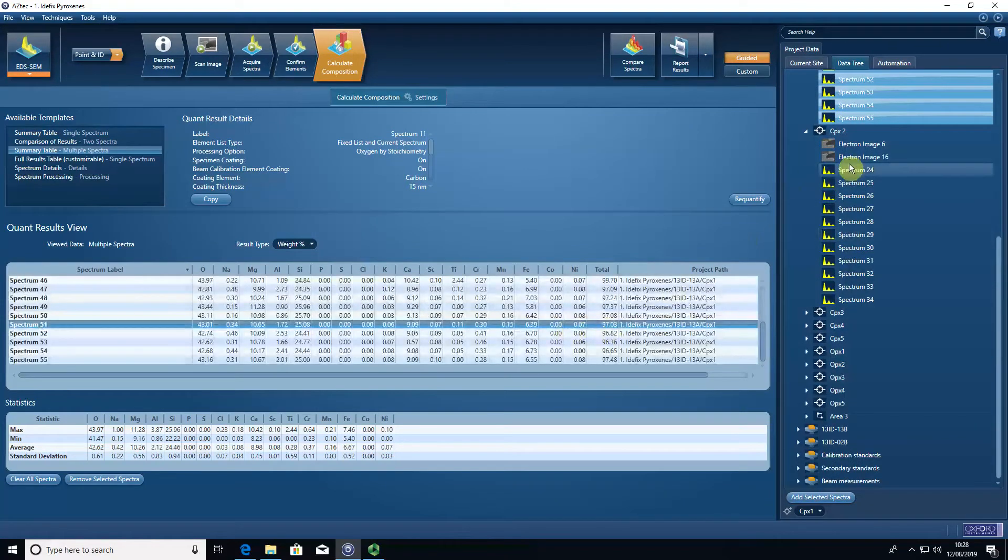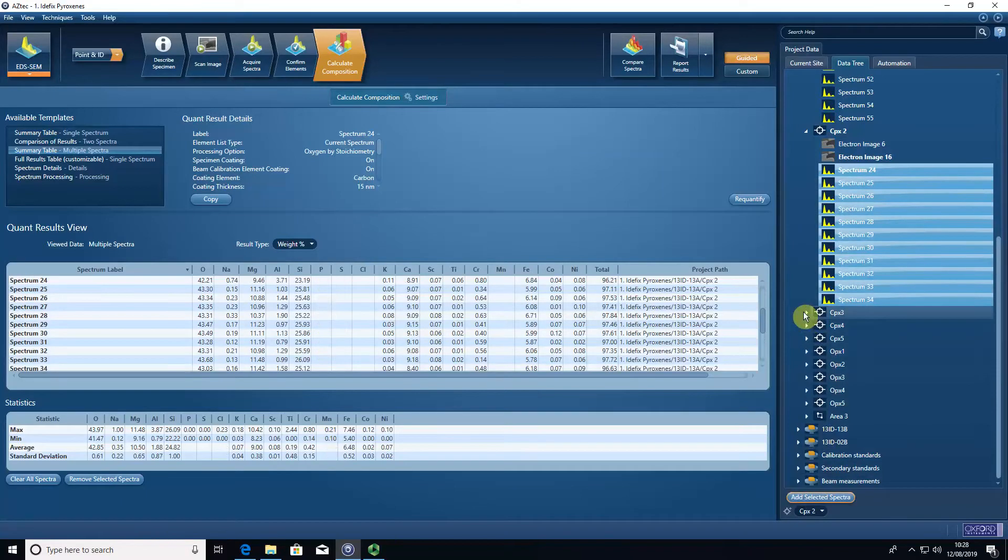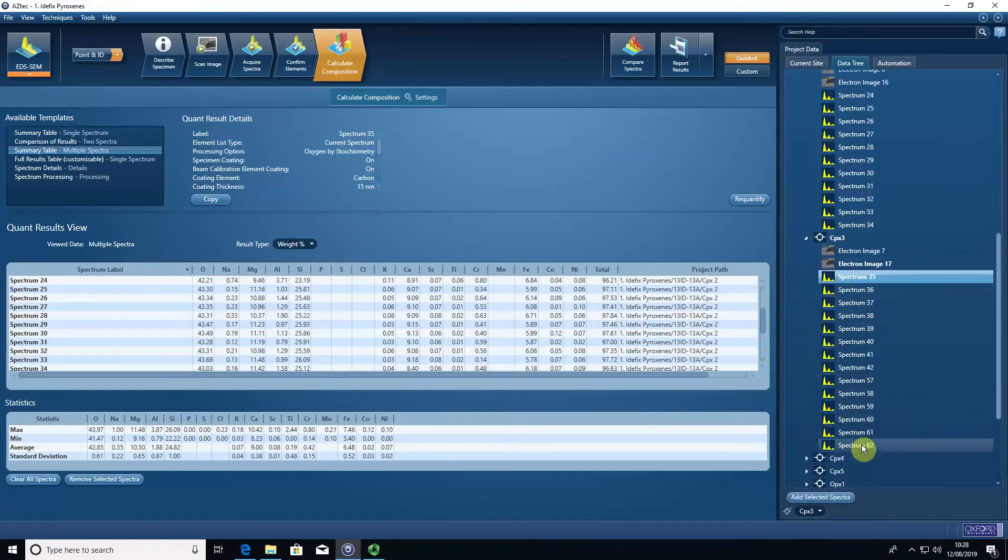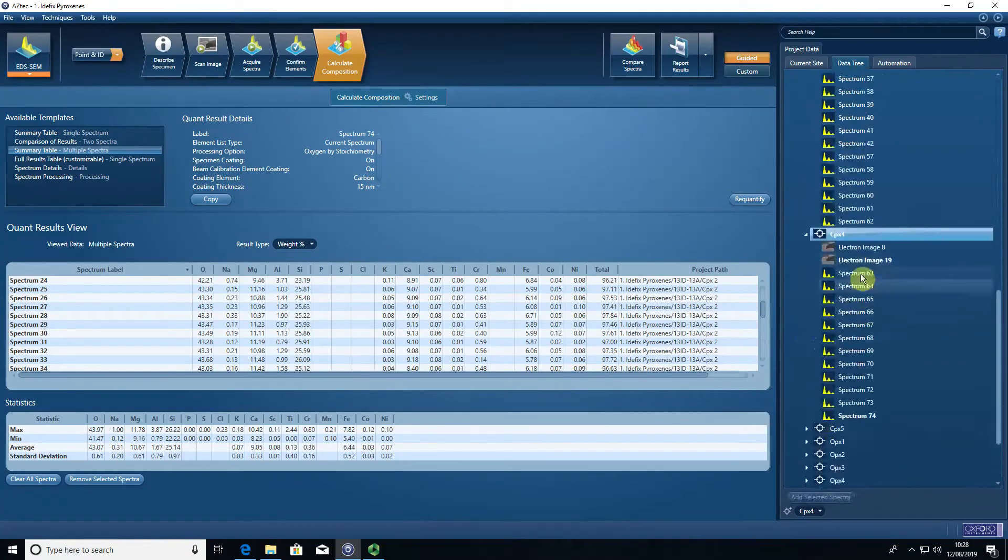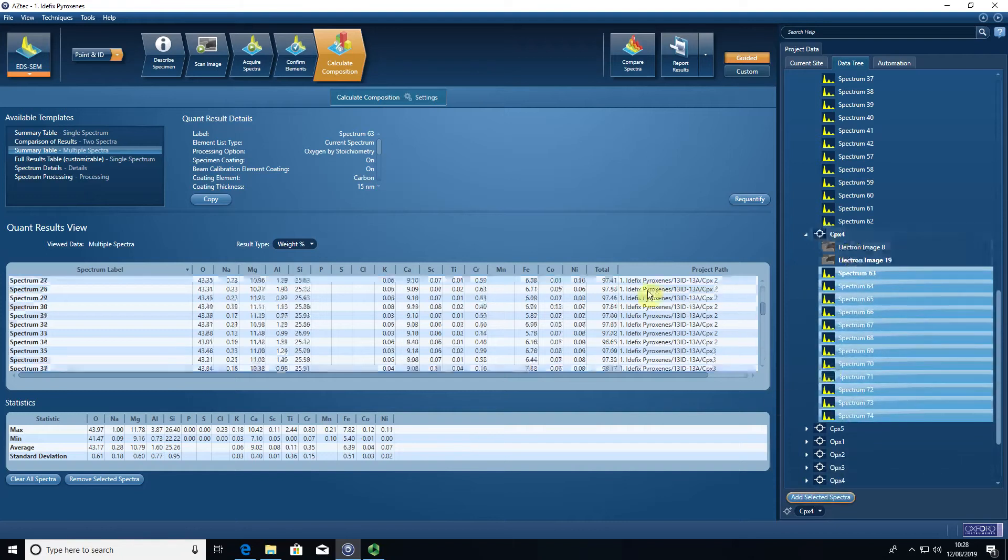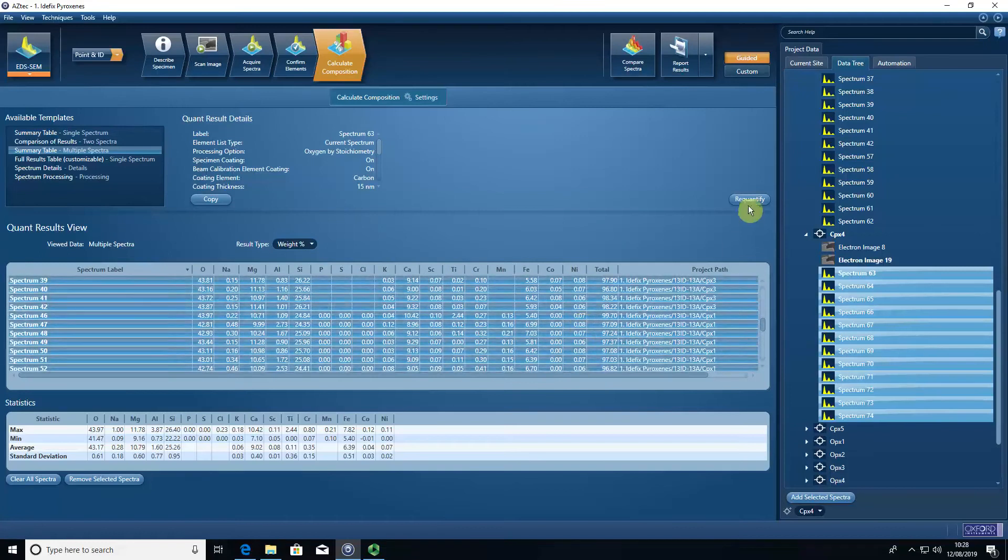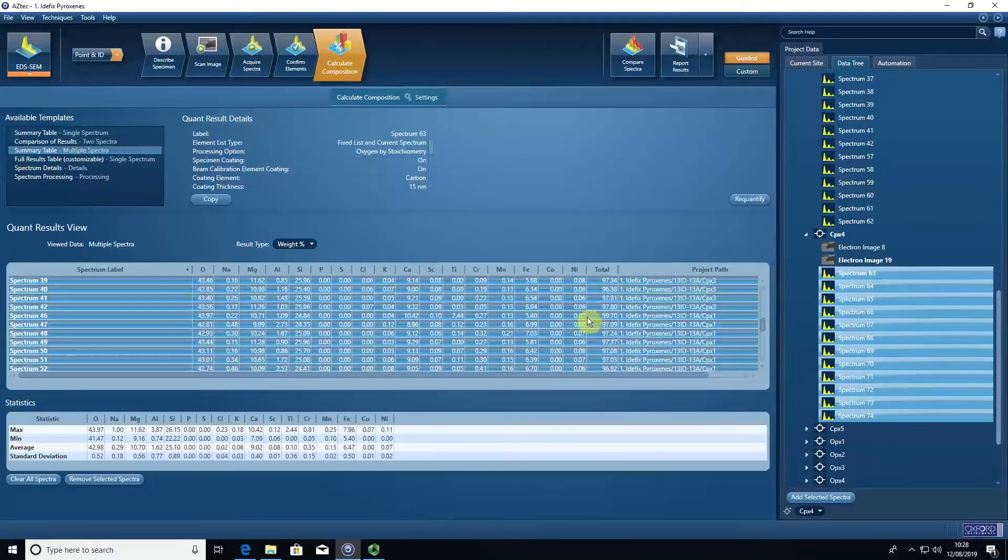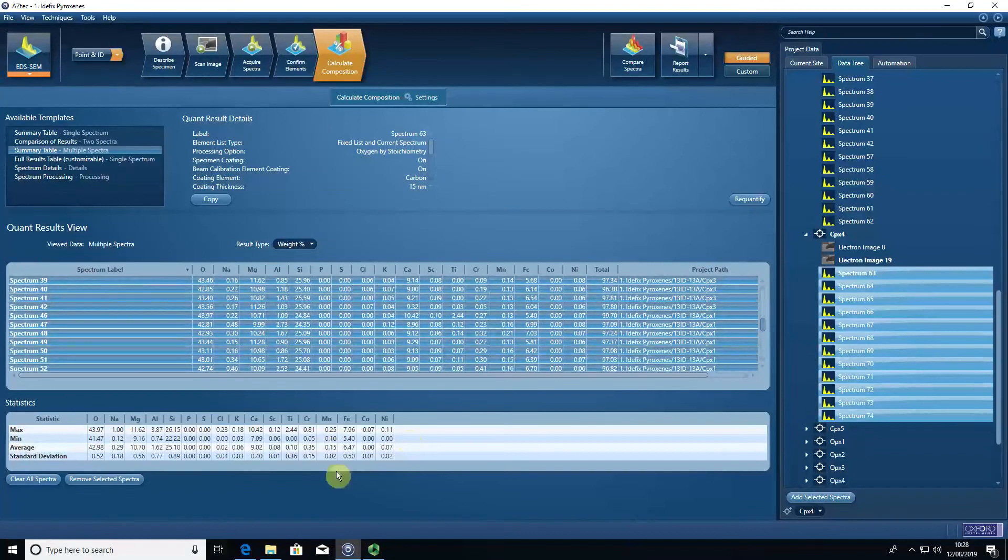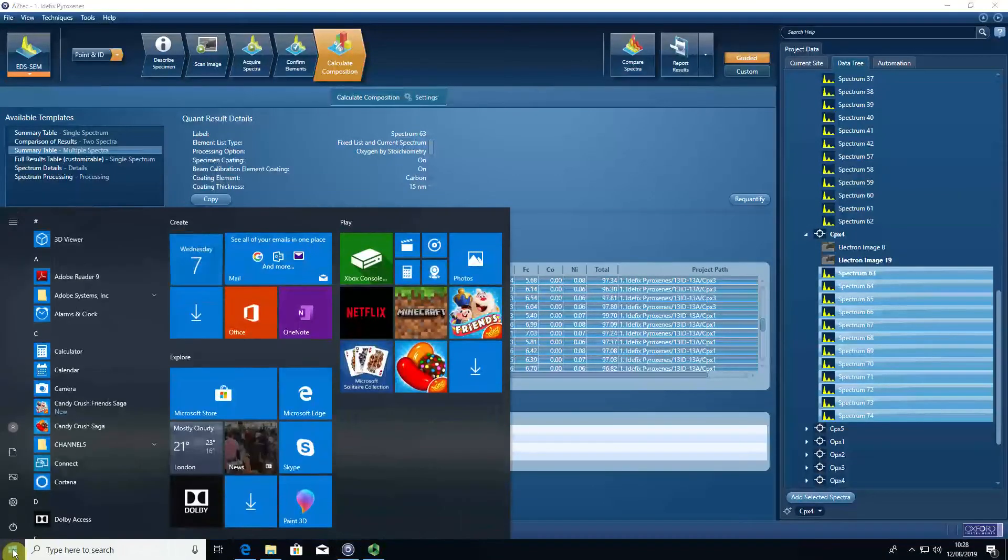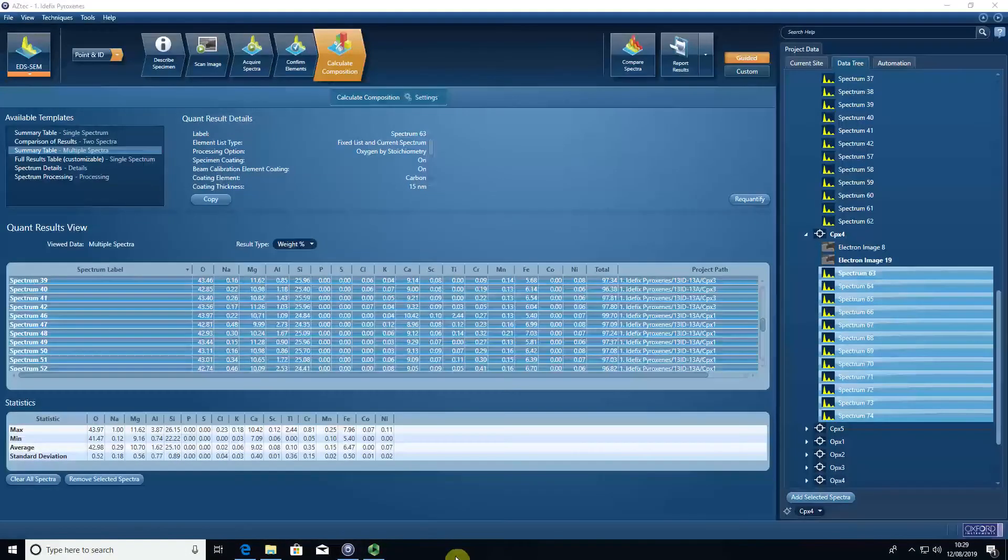The easiest way to do this is to add all your spectra at the very beginning. As I say, it's recommended to do this at the point of acquisition rather than the next day because you never know if someone's going to mess around with your standardization without you knowing by accident. Let's say we've added all our spectra, then we can just click on it. Ctrl-A will select all as well. We re-quantify before we copy, select them again, copy them out, and then it would be a case of going to Excel and copying into Excel, and that's that done.